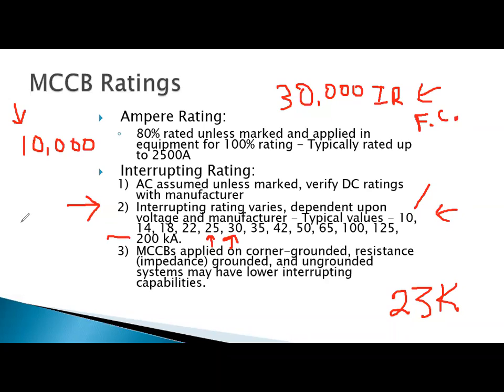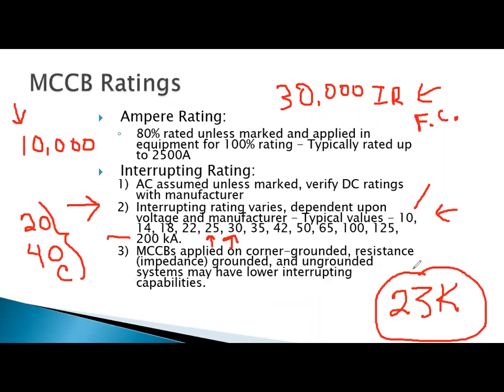Normally, what we would pay attention to is the rating on the handle. Is it a 20 amp breaker? Is it a 40 amp breaker, or whatever it is on the handle? Well, that's fine. And that would protect my conductor, no doubt about it. Other than a motor circuit, it probably protects my equipment. But we have to pay attention to what's on the side of the breaker and not always what's on the handle. And what's on the side of the breaker would be the interrupting rating, and make sure that it is higher than whatever the available fault current is.